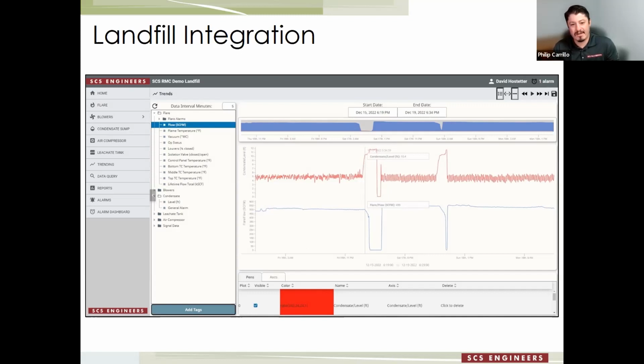We have a blocked header or a blocked system, and we need to address it. It could be a thermocouple that went bad, it could be a blower. We go back to that event, look at the analytics on that shutdown, and we can quickly identify the issue.